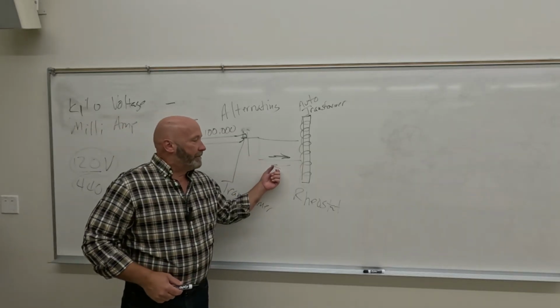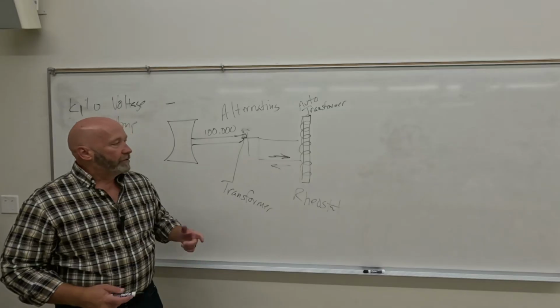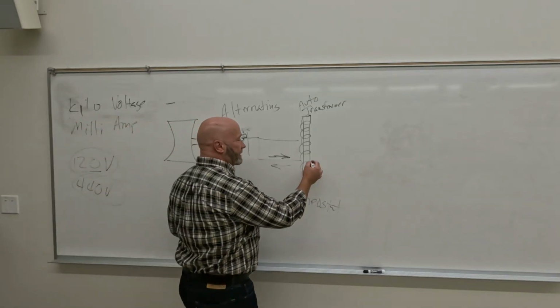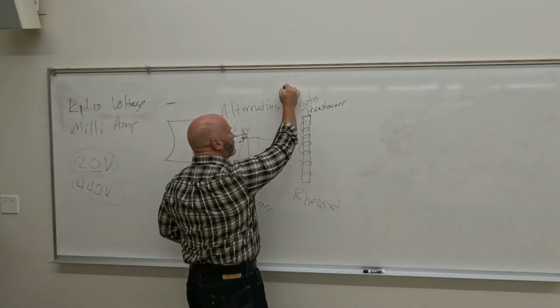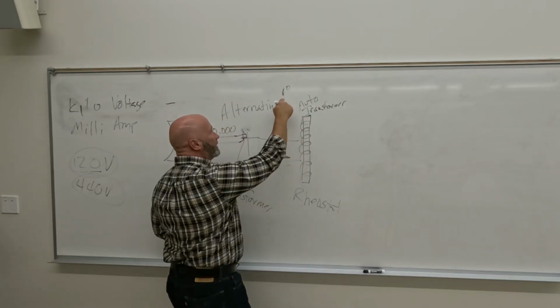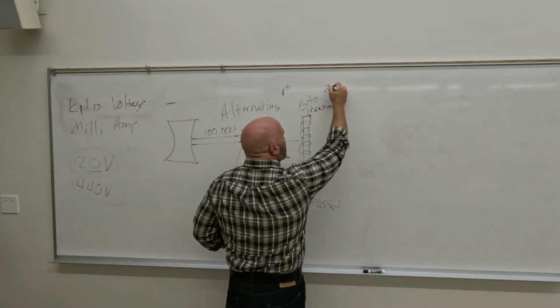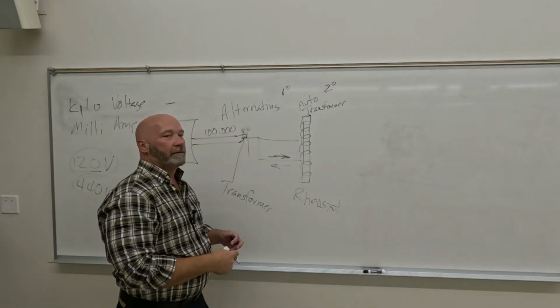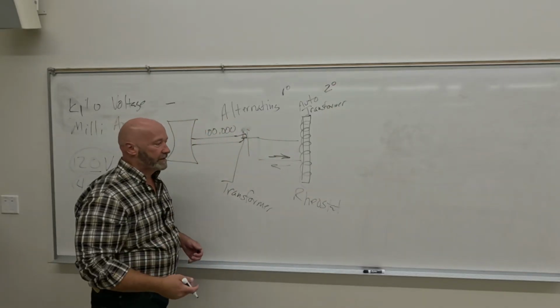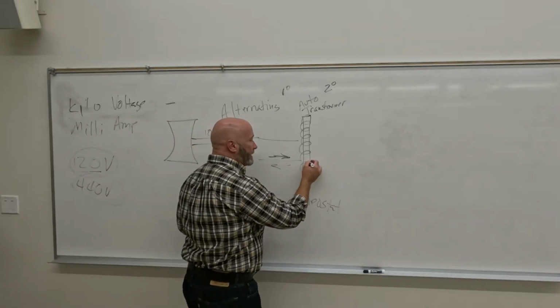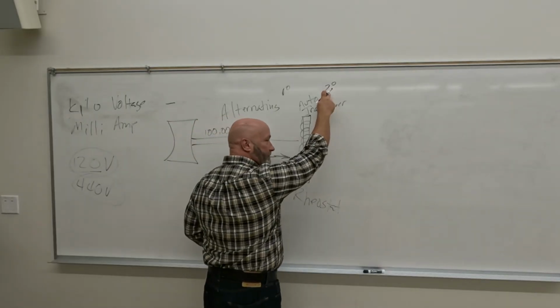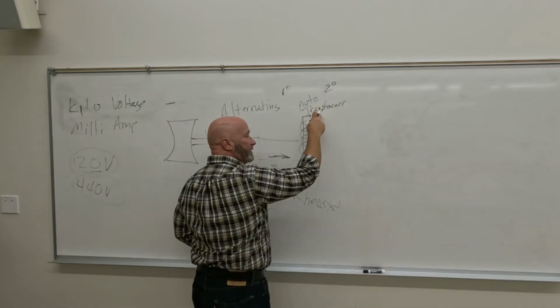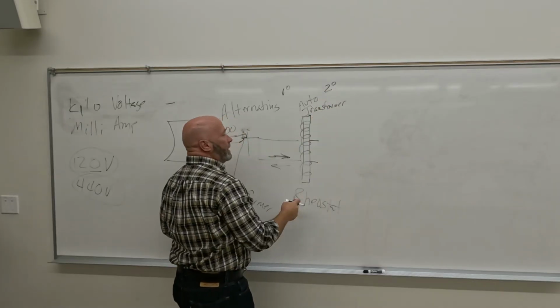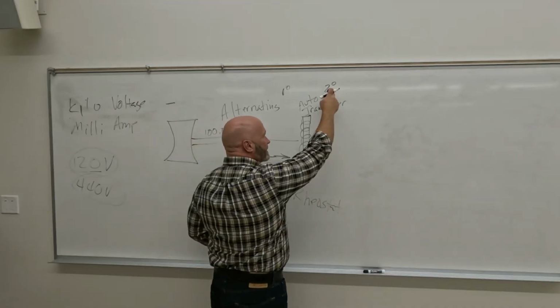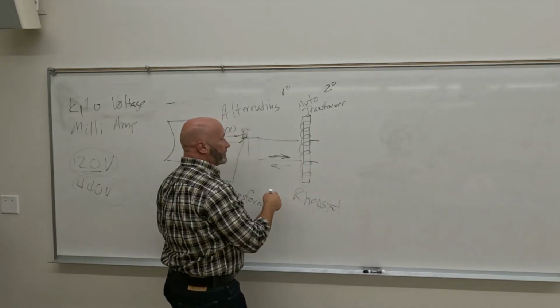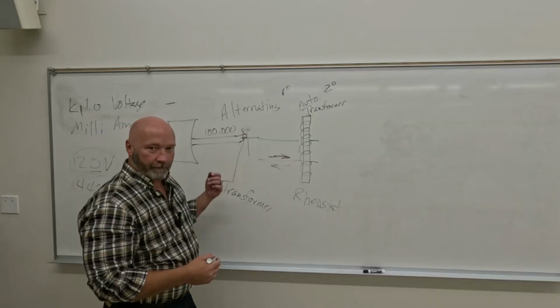So we use that magnetic field to adjust our voltage, so that if we were to plug into the secondary side - we're going to call the side that we give the electricity to the primary, and that's what that 1° means. A secondary side is the side we don't supply electricity to; we're going to get electricity out of it. But if we plug into the exact same spot on the secondary side of the auto transformer, then our voltage out is identical to the voltage going into the primary side.